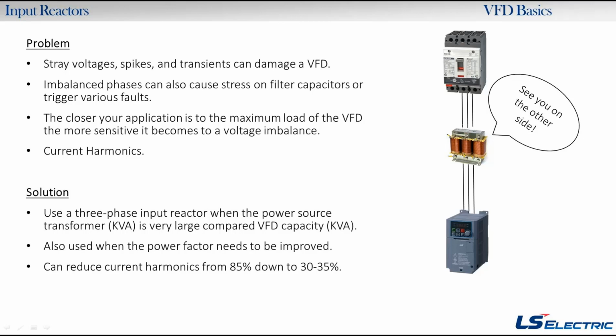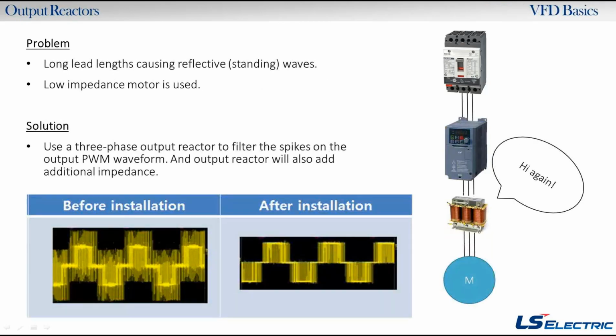Now you notice the reactor is telling us something. It says, see you on the other side, because we have the same thing for an output reactor. It's the exact same device, the exact same component, but you move it from the input of the drive to the output. Now it becomes an output reactor, or a load reactor. These are used if you want to protect the motor or the output of the drive. So if you have long lead lengths, and when we say long leads, that can be like 100, 150 feet or longer, we recommend putting a load reactor between the drive and the motor.